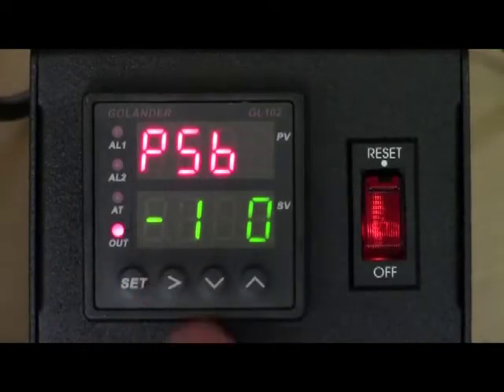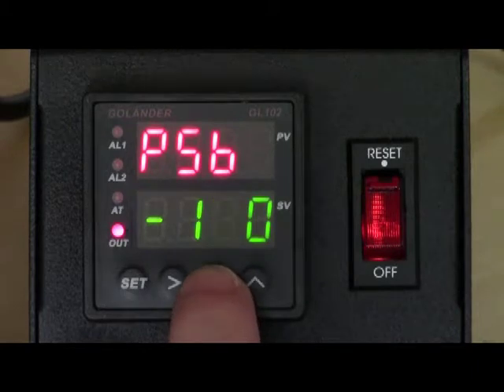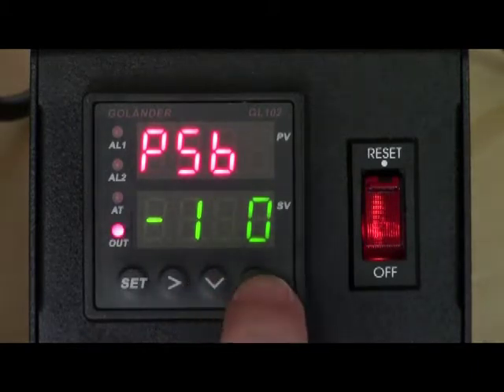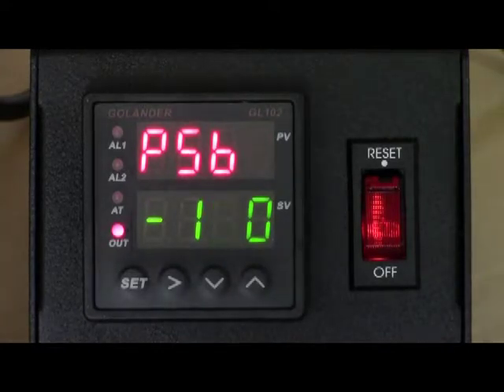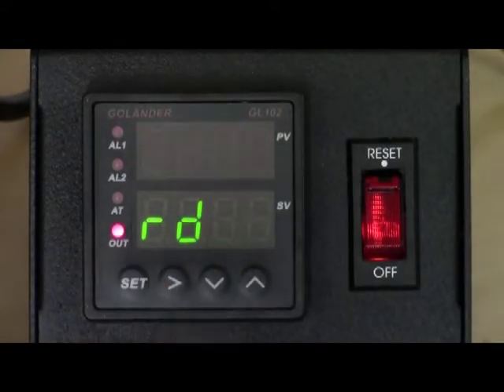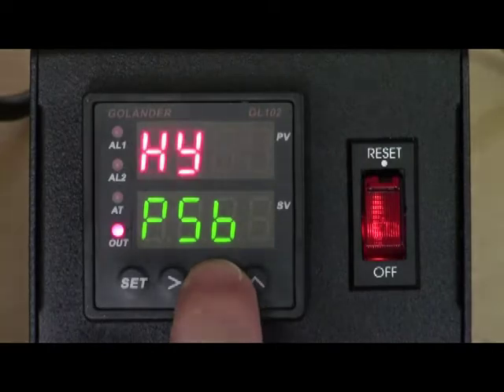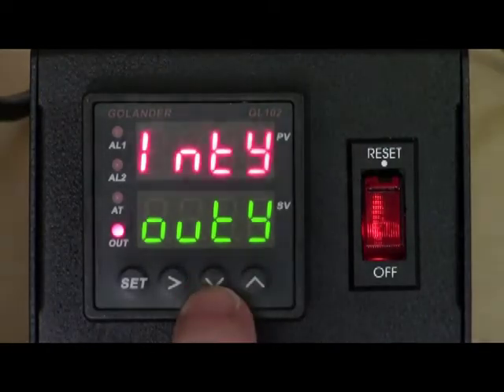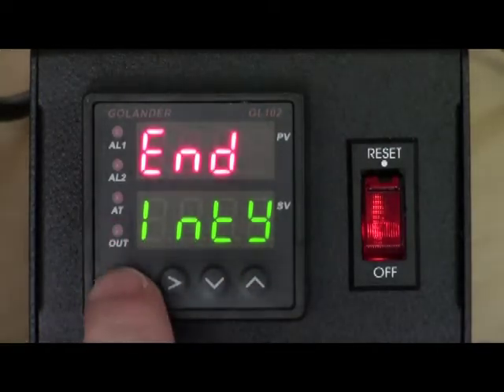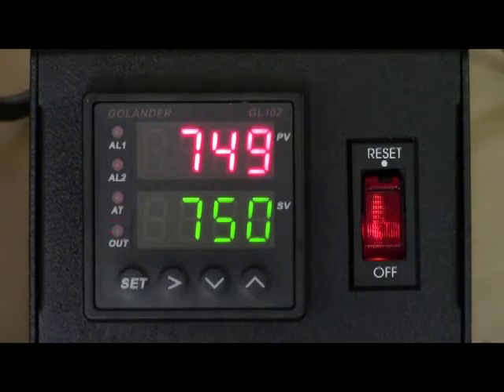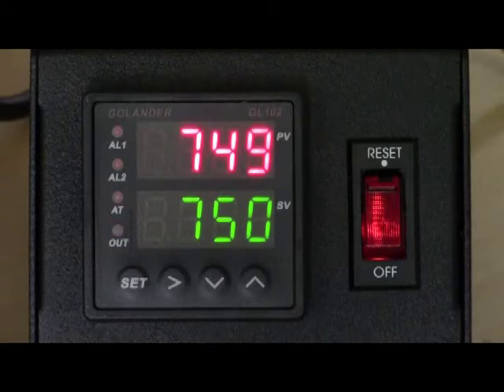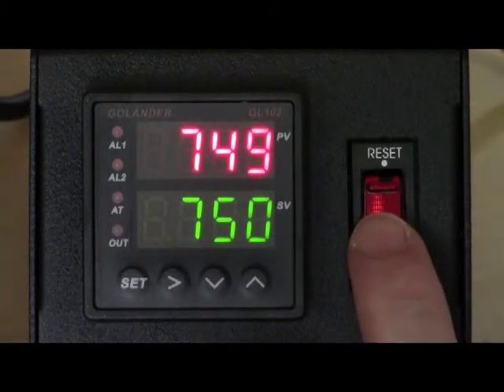Using the arrow buttons, change the current offset information in the SV display to show the new offset information that has been determined. With the new offset information showing in the SV display, press the set button, then use the up and down arrow buttons to change the operating parameters in the PV field to end, and press the set button again. When the temperature is stabilized and the solder pot is idling, the verification and calibration process can be repeated as necessary until the desired results are achieved.